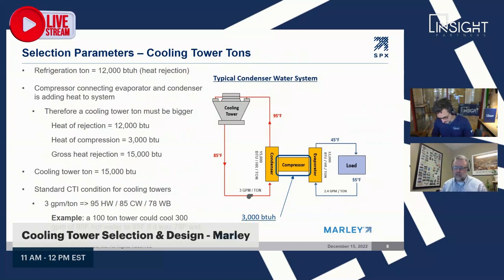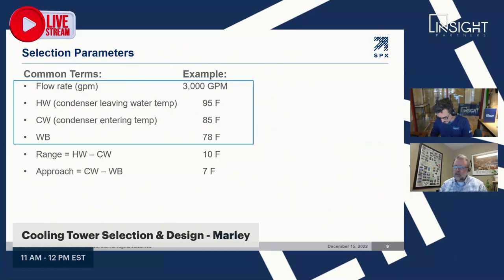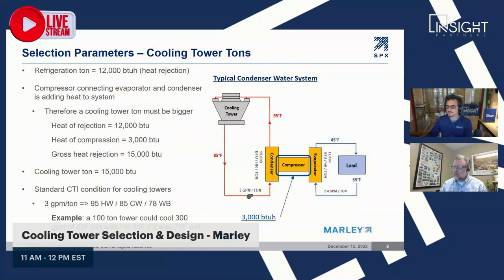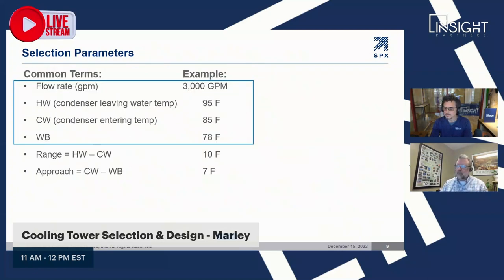This ton methodology is fine for initial selections and budget requests to get initial layouts and sizing. However, for a more precise selection, we typically recommend using flow rate, hot water temperature, and cold water temperature — these give you an actual heat load. Today's chillers are much more efficient and may not add 3,000 BTUs, so there's often a little extra padding when using the ton-based approach.